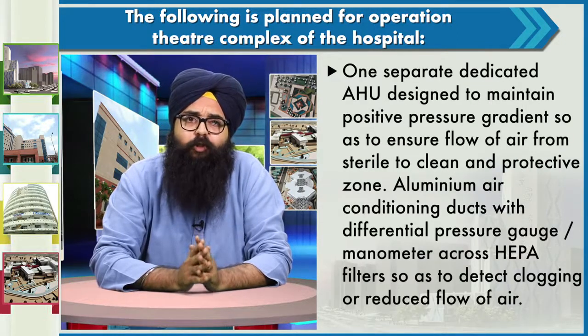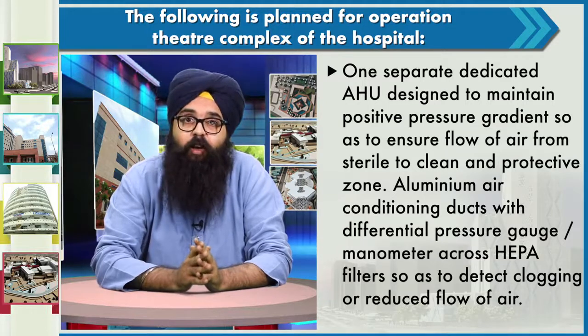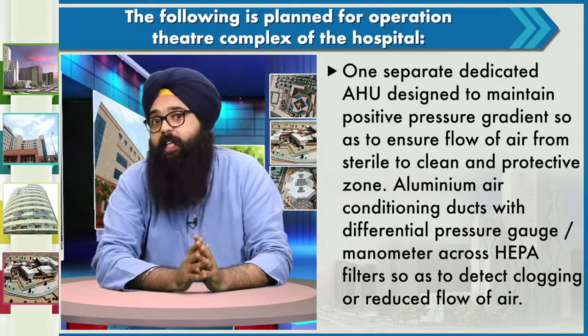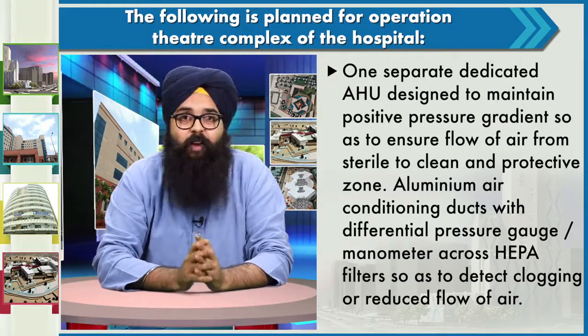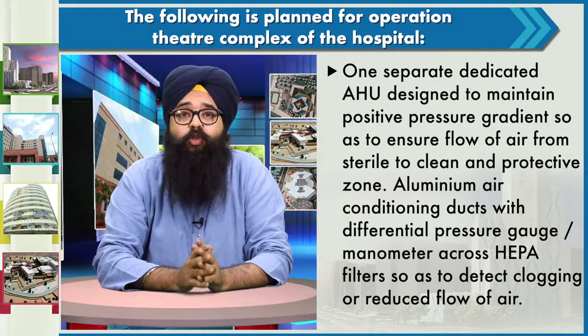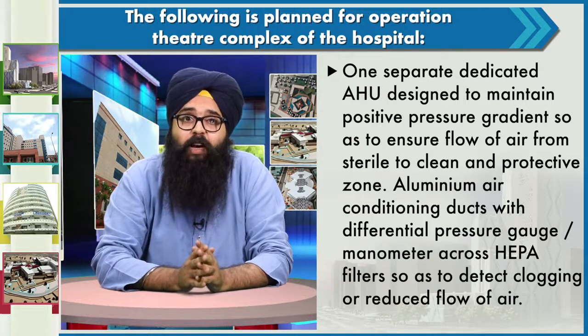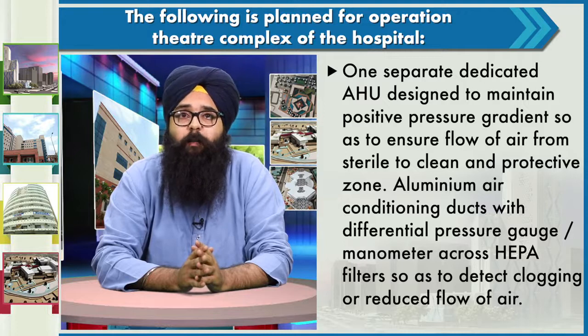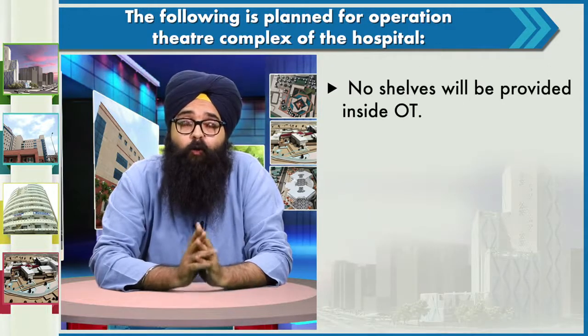One separate dedicated AHU — Air Handling Unit — is essential as part of the total HVAC system. Under no circumstances should AHU air from the OT suite intermix with other suites. The dedicated AHU must be designed to maintain a positive pressure gradient so as to ensure flow of air from sterile to clean and protective zones. Aluminum air conditioning ducts with a differential pressure gauge manometer across HEPA filters, to detect clogging or reduced air flow, must be provided. There should be no shelf provision in the OT.